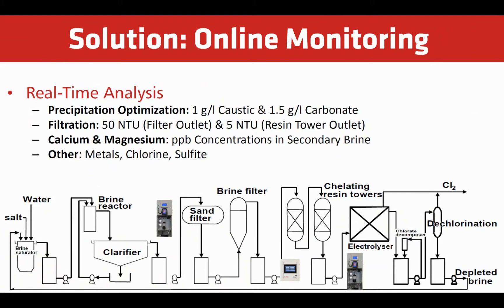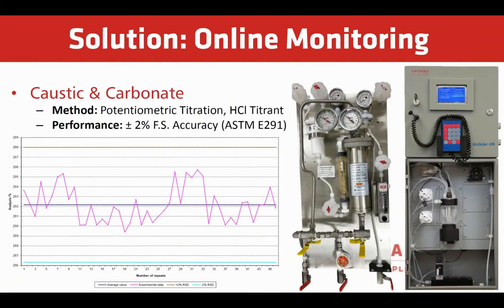Other compounds can also be measured if they are known to be an issue in your process. Accuseries is Galvanic's third-generation wet chemistry analyzer. One system can measure both caustic and carbonate following approved ASTM methods, with a performance of plus or minus 2% of full scale, which ensures accurate precipitation of impurities. For brine samples, we recommend a special sample conditioning system to cool the sample; this equipment continuously flushes the lines in order to prevent any scaling issues.